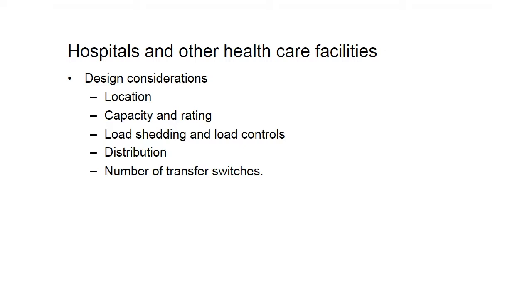And then as you're looking at all these different kinds of loads, you want to start taking into consideration the priorities. So obviously your highest priority are your loads that are required by code. The optional loads are things that are nice to have, all fall towards the bottom of the list. So as you're looking for an overall system design, and oftentimes when you parallel generators, you want to plan for the unlikely event, hopefully, that one of the generators would fail either during operation or during startup. And how do you handle that from a system perspective and a design perspective? You need to prioritize those loads, and you do that as you go through the design process.